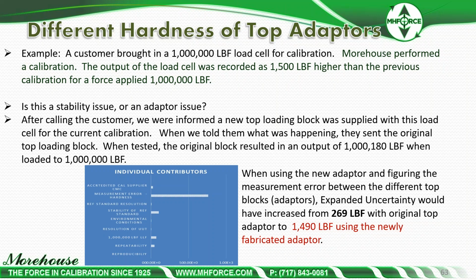You just go set it up, do everything right. All of a sudden, you set this up, and it's 1,500 pounds off. It's like, that doesn't make any sense. Year after year I've done this, and it's been a pretty darn good load cell. Why has it drifted that far out? So you start saying, hey, is a strain gauge coming loose? Is something weird? Are my connectors okay? Is it stability or an adapter issue? Well, prior to this, I had not really seen the effect of top adapters on a load cell, and I called the customer and said, hey, we have a 1,500 pound error.